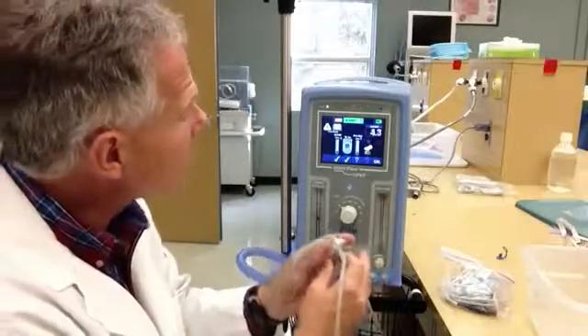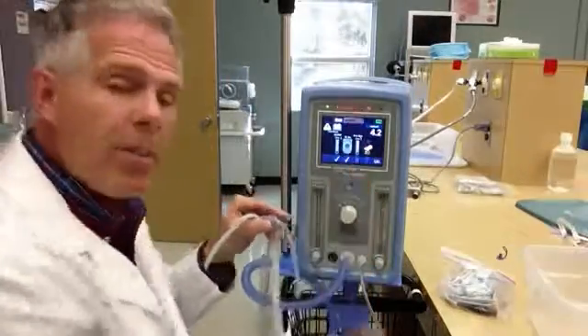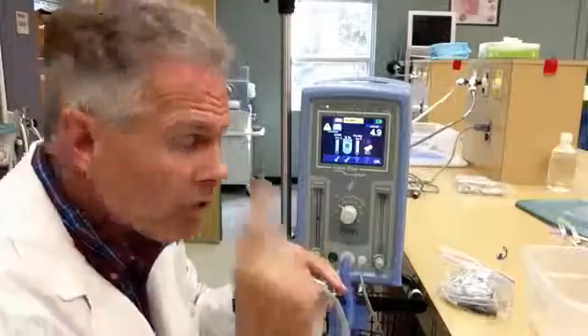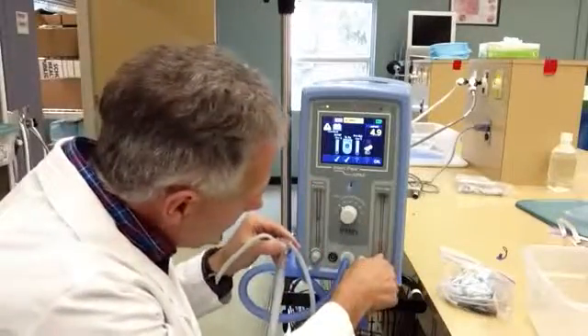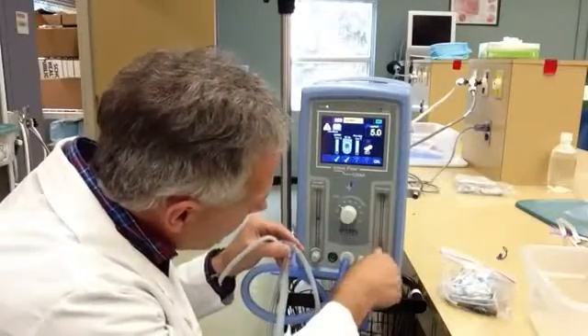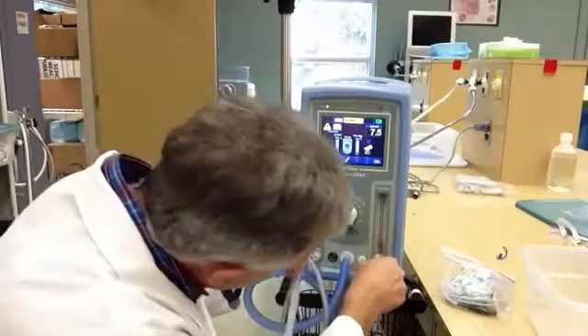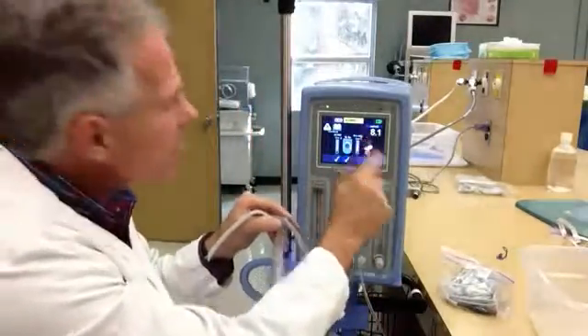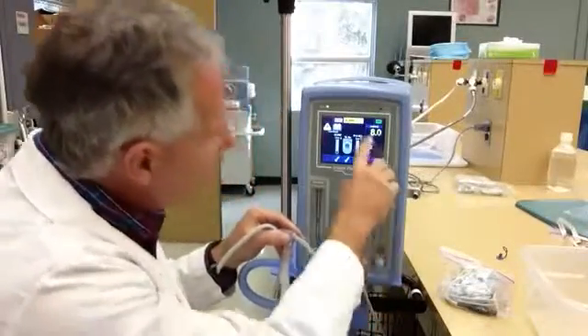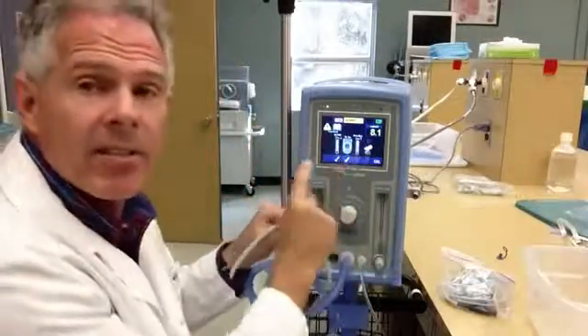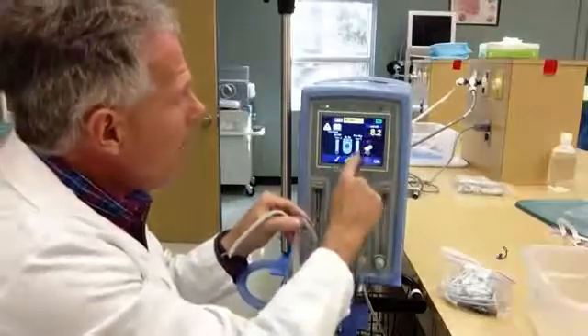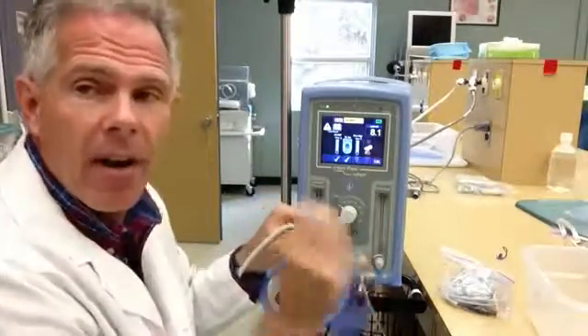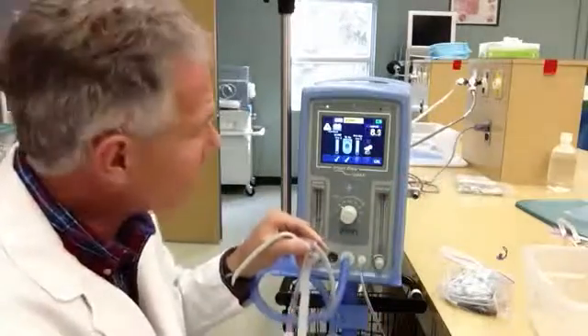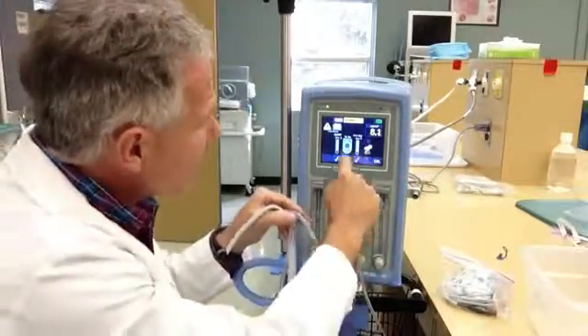All right. Now it says, what about my high pressure or my pressure control level? Do I have that set? So I'm going to add some flow now, and I'm going to set that at 3 liters per minute. All right. And at 3 liters per minute, this should go up to plus or minus 1 centimeter of water pressure to 8. All right. So I've set up my high pressure at 8 and my CPAP pressure at 5. Okay, that's not a bad place to start. Okay, so I'm going to check that off.